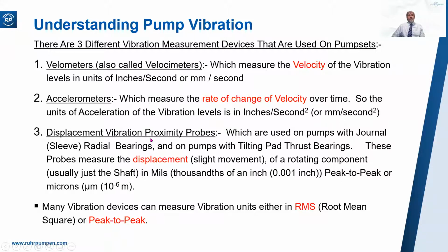The third one is displacement vibration proximity probes. These are used in pumps which have journal, sleeve, radial bearings, and tilting pad thrust bearings. These probes measure the displacement, the slight movement of a rotating component, the shaft. And so the measurement is in mils, thousandths of an inch, or microns, a peak-to-peak reading.